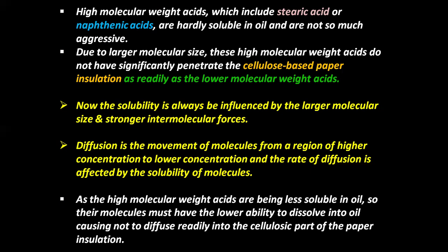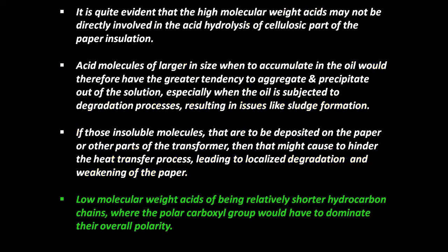As the high molecular weight acids are less soluble in oil, their molecules have a lower ability to dissolve into oil, so they do not diffuse readily into the cellulosic part of the paper insulation. It is quite evident that the high molecular weight acids may not be directly involved in the acid hydrolysis of the cellulosic part of the paper insulation.